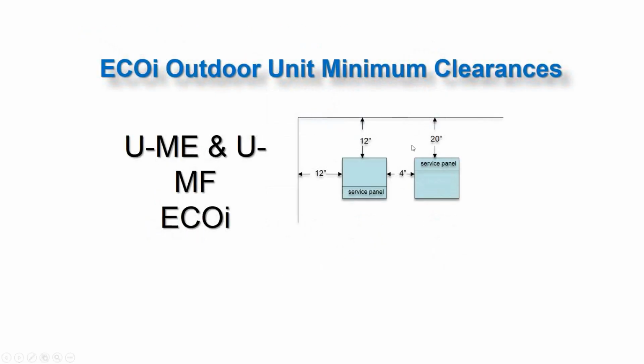Okay, these are our outdoor unit minimum clearances for the ME and MF unit. So our 3-phase heat pump and our 3-phase heat recovery unit. We want to watch out for our service panel. We want to be mindful where we're installing, what side of the unit the service panel is on. So when you've got a wall here like this, we want to see 20 inches minimum, 12 inches from the side of the unit, and 12 inches from the back of the unit. These units discharge, the fan is on top, and they blow up, so you don't have to worry about blowing into another unit like you would with the LE unit.